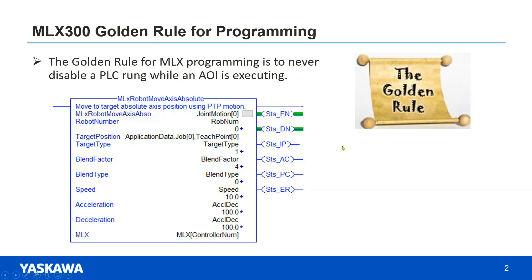The motion commands are slightly different. They have both a status done bit and a status process complete bit or STS PC. With these commands, the done bit indicates that the motion has been placed in the queue and the process complete bit indicates the robot has reached the position.